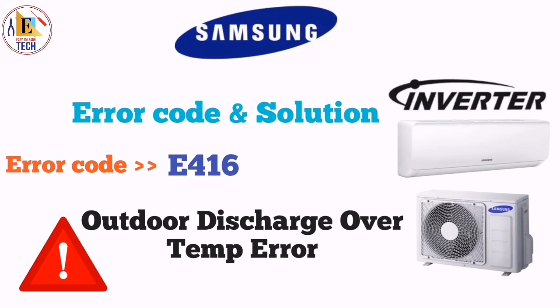When you see error E416 in your outdoor unit, it means outdoor discharge over temperature error or compressor overheat error. First of all, we have to check these 3 points. First, check the discharge temperature in the outdoor unit. Second, check for compressor locking or gas leakage. Third, download the EPROM data. Let's see the troubleshooting procedure.